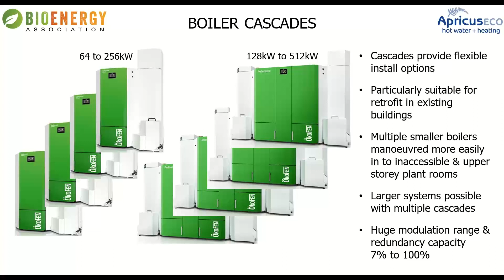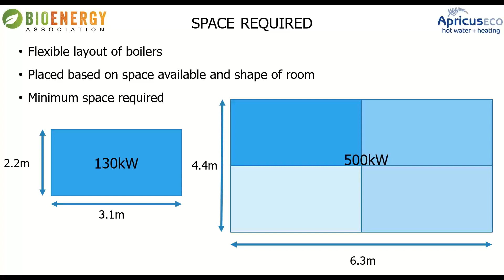Really important to understand when we're trying to apply this in a modern scenario. And it goes back to, what is your actual heat load? What is the requirement that you need? How can we make sure that we're meeting it in the most effective way? So if we look at the space required, as I said, they're pretty flexible. This is the space required, including clearances. So 130 kilowatts we saw back at Palmerston North. We've got 2.2 by 3.1 meters. Now you can just plug them together to get a 0.5 meg. And because we've included clearances, it's maybe a little bit tight. It'd be nice to have a little bit more room, but it's possible to do it in less than 4.5 meters and less than 6.5 meters. And you've got 0.5 meg there. It doesn't include the fuel store, but we'll come to that in a sec.